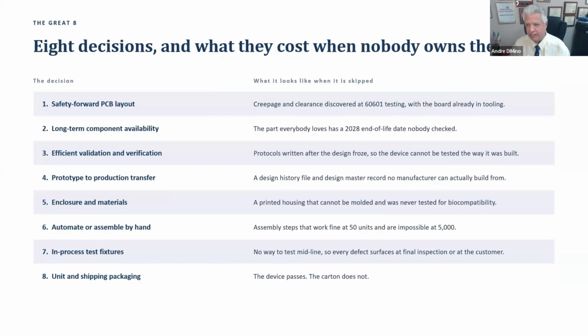So this is a terminology that we came up with, the great 8 of DFM. The great 8 are things that you need to apply before you look into a design. For number one, I mentioned it in one of the slides before, in the photos I had: creepage and clearance is important for the PCB layout. So you want to make sure that it's set up properly before that board is finalized. Number two is component reliability and component availability. Make sure that when you design something, it doesn't have a short end of life. Number three, are you able to test it? Can you do validation and verification so that it can be tested in different ways? Number four, do you have design transfer ability with your design history file and a device master record? It says design master record; it should say device master record, so that any manufacturer can build it.